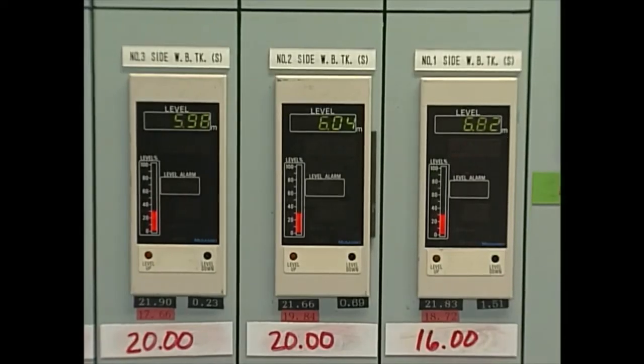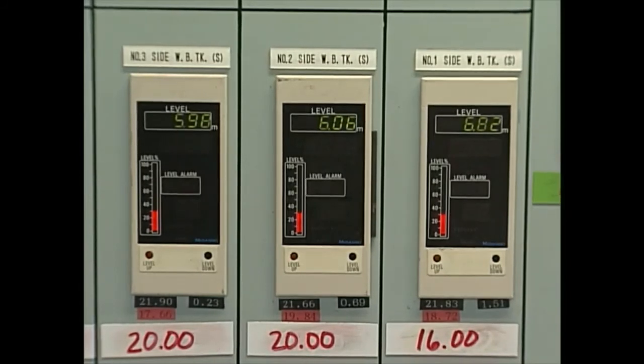Watch water level since cavitation occurs as the level drops, which causes the water head pressure from the pump's suction valves to decline.